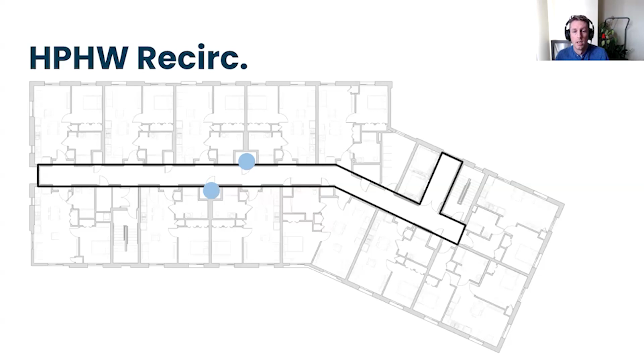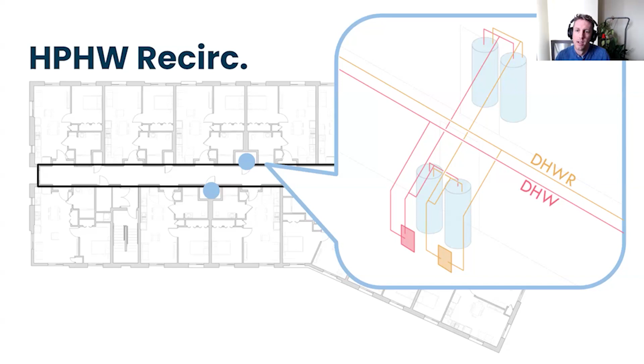We were able to put the 4 heat pump hot water heaters, distributed 2 each, in those closets. And then we have a recirculation loop per floor for the water with an aquastat on the return side, just measuring the temperature of the water, making sure that it's still at the design spec. And then we have a mixing valve on the hot water side directly next to the tanks to make sure that if the water temp does get low, it can feed some more hot water back into that system. This was a little bit funky because we have 2 closets that are remote from each other that are both feeding the same recirc loop. So we had to pipe up and over our corridor to get to the aquastat and the mixing valve, but it's working completely as intended.